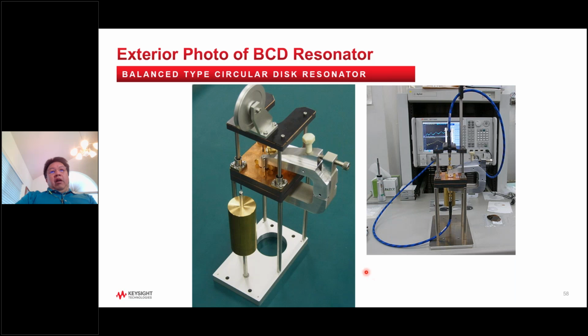Now the BCDR. In this picture you can see it, and this is actually up to 67 gigahertz. You connect the cable to the analyzer and connect here. Basically, this method requires a two-port calibration because the measurement is broadband. We want to make sure we can tell the signal at the resonance versus the noise floor.